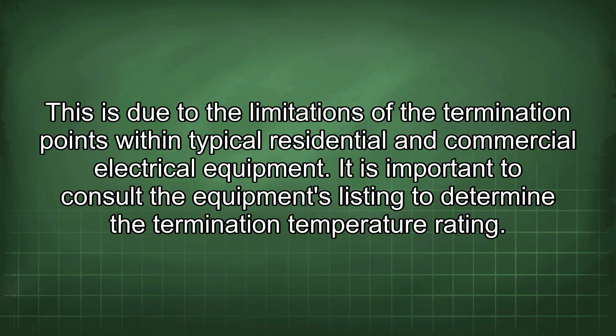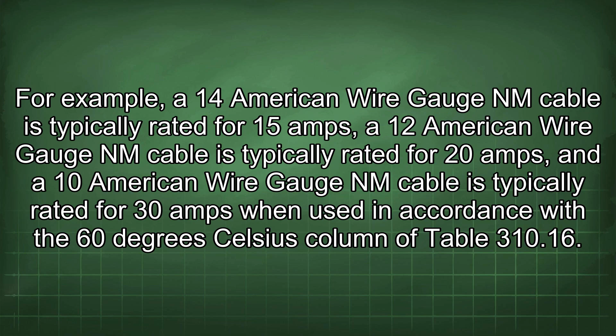For example, a 14 American wire gauge NM cable is typically rated for 15 amps, a 12 American wire gauge NM cable is typically rated for 20 amps, and a 10 American wire gauge NM cable is typically rated for 30 amps when used in accordance with the 60 degrees Celsius column of Table 310.16. Remember that these are general guidelines, and the specific installation conditions may require adjustments to these ampacities.